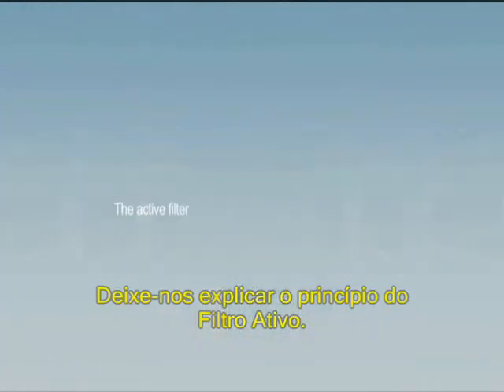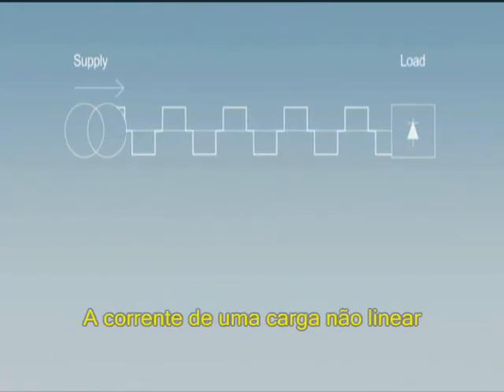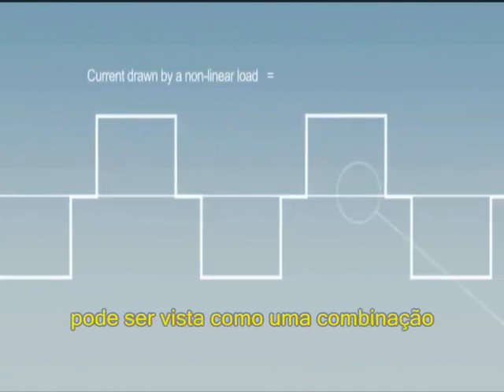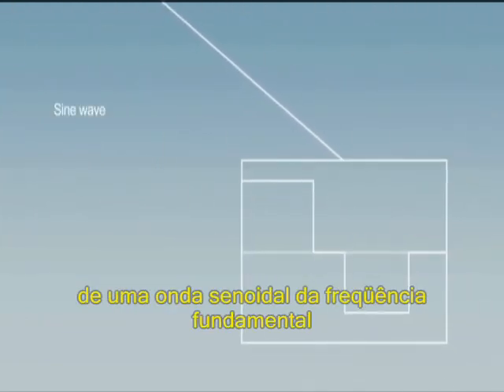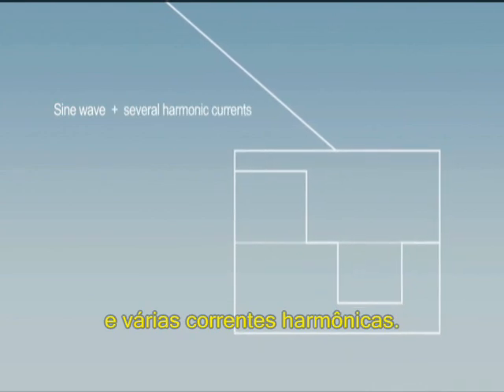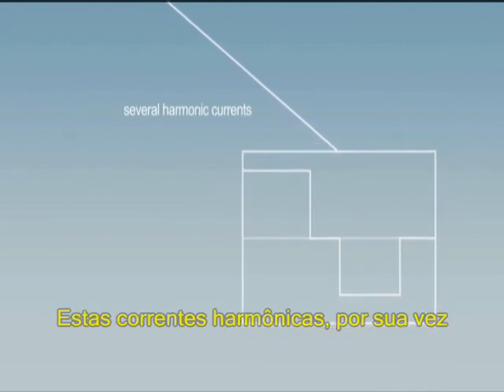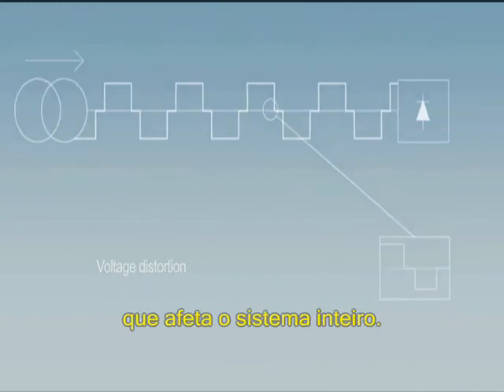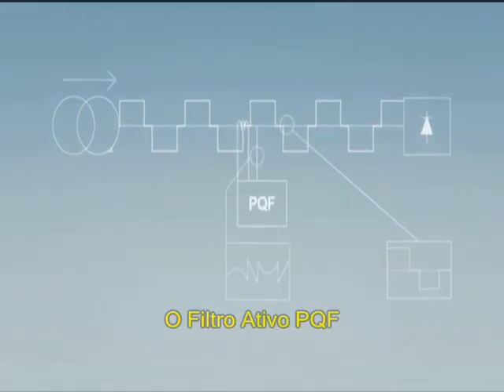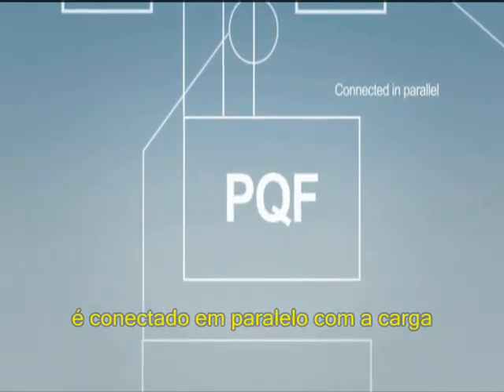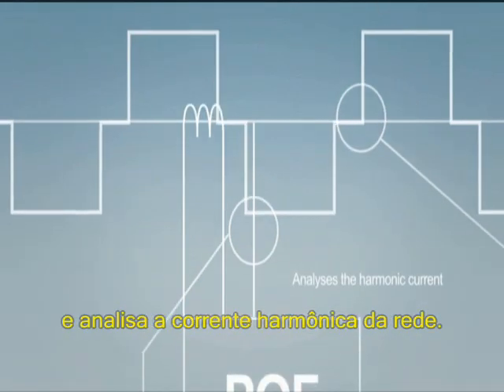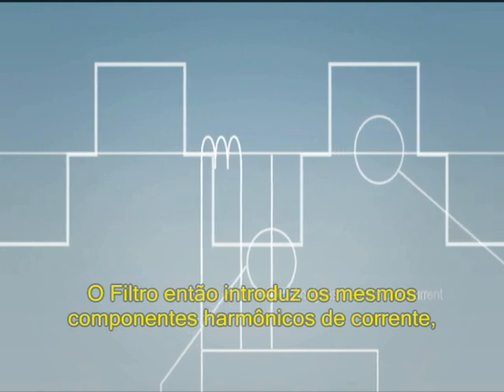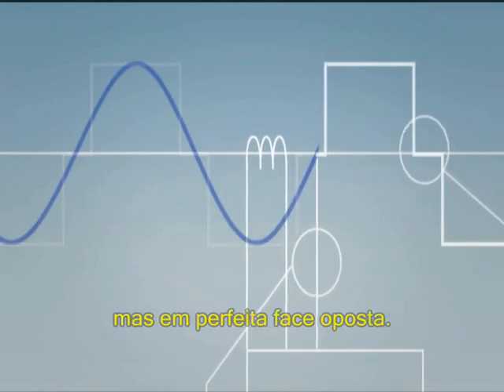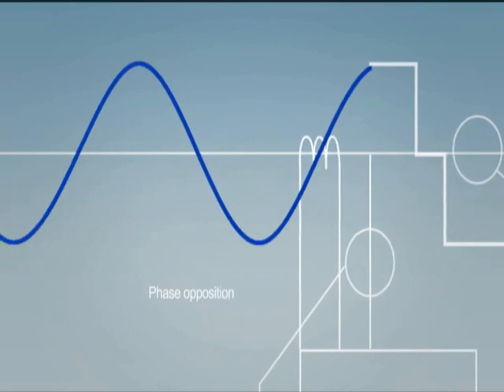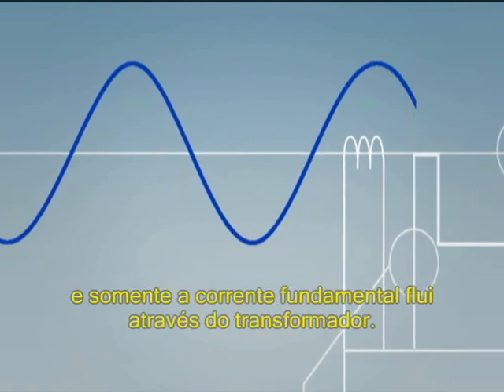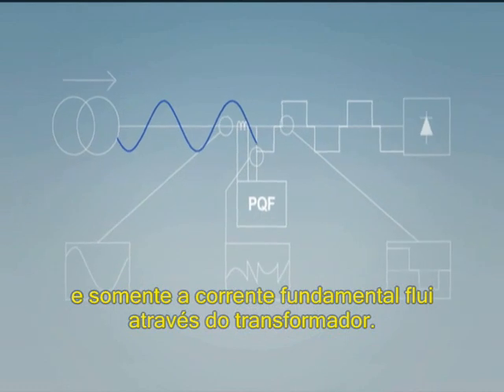Let's now explain the active filter principle. The current drawn by a nonlinear load may be seen as a combination of a sine wave at the fundamental frequency and several harmonic currents. Those harmonic currents in turn create voltage distortion which affects the whole system. The PQF active filter is connected in parallel with the load and analyzes the harmonic current drawn from the network. It then injects the same harmonic current components as the load, but in perfect phase opposition. The harmonics are thereby cancelled, and only the fundamental current flows through the transformer.